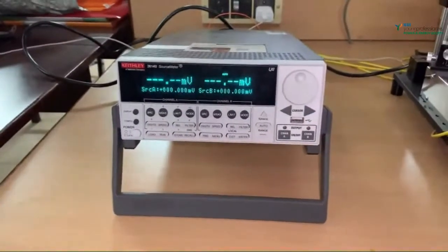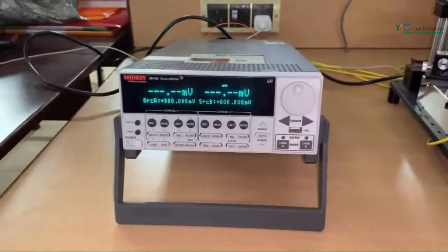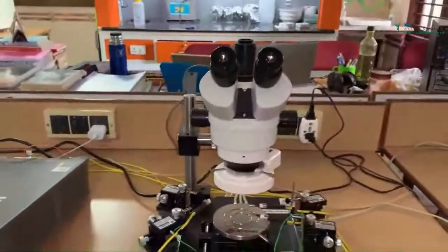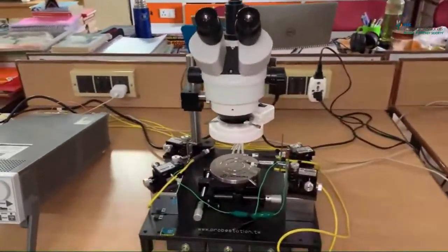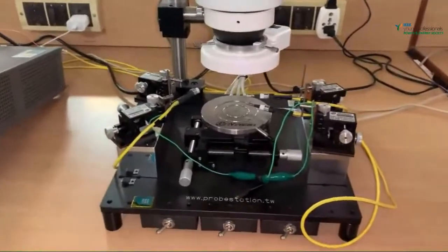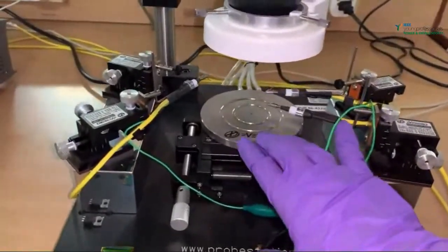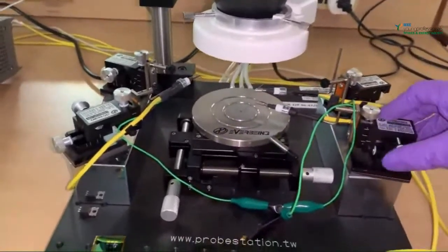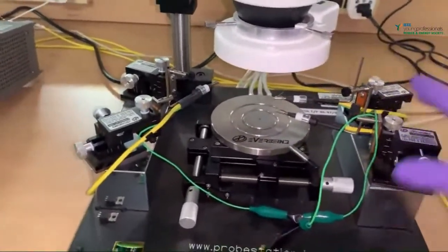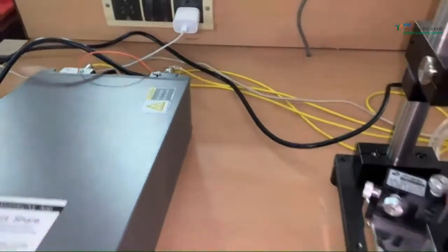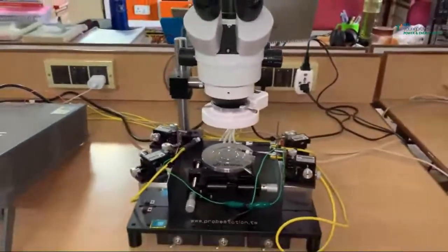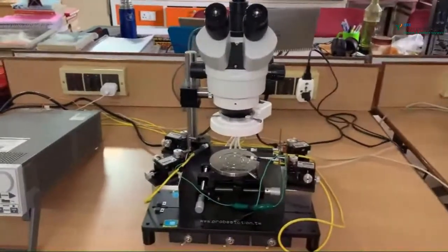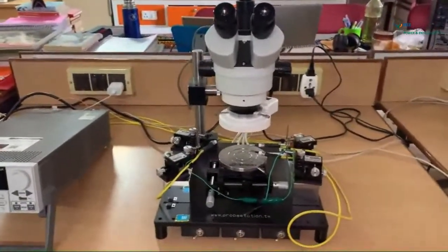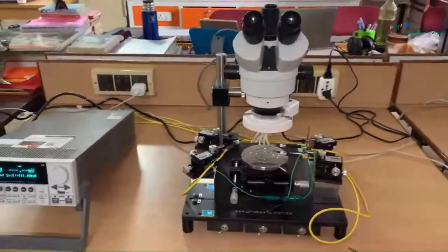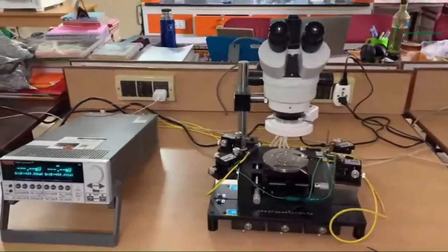This is the source meter. This equipment, along with the DC probe station shown here, has a microscope as well as a chuck where the device will be placed. So this is the chuck. Here the device will be placed and it will be probed using these manipulators. These manipulators will be connected to the source meter through this cable. And the source meter will be connected by USB cable to the system. So through software, the IV characteristics, as well as the transient response, etc., can be obtained.